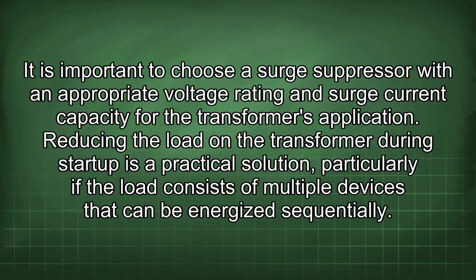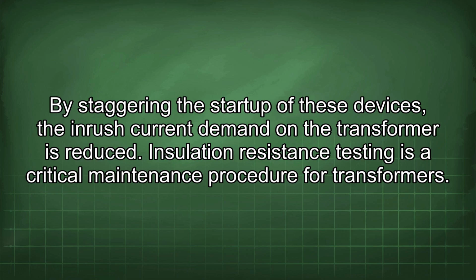transformer's application. Reducing the load on the transformer during startup is a practical solution, particularly if the load consists of multiple devices that can be energized sequentially. By staggering the startup of these devices, the inrush current demand on the transformer is reduced.